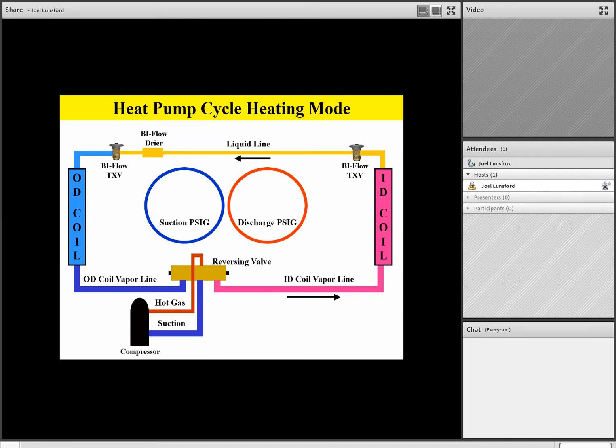We take that hot gas, we condense it into a liquid, and we pass it through the indoor biflow TXV. We then have that liquid coming down the common liquid line through the biflow filter dryer, where it enters the biflow TXV on the outdoor coil in the heating mode of operation. That outdoor TXV then meters refrigerant into the outdoor coil, which is acting like an evaporator in the heating mode, and it's cold. And so the refrigerant boils off in that evaporator, absorbing heat from the outdoor air, and that cool vapor then goes down the outdoor coil vapor line, loops through the reversing valve back to the suction of the compressor. You'll also notice that the gauges have not changed.